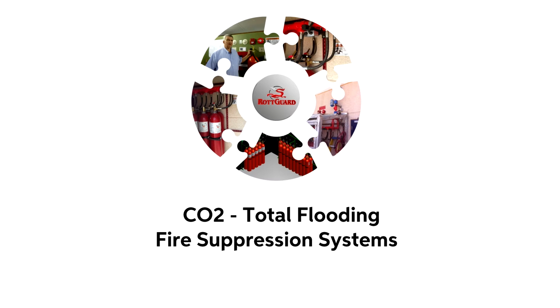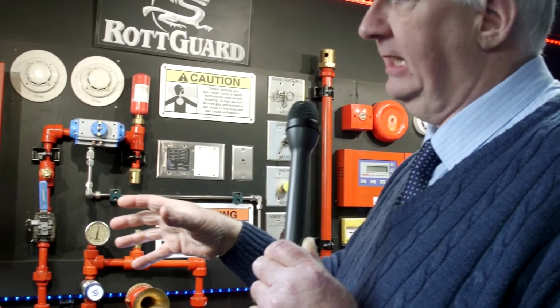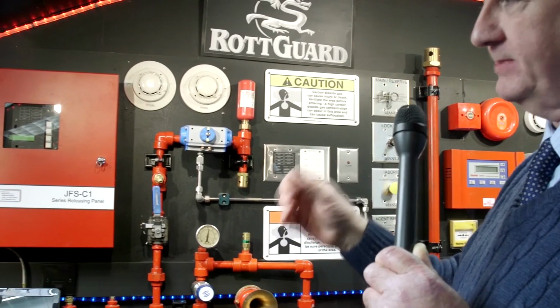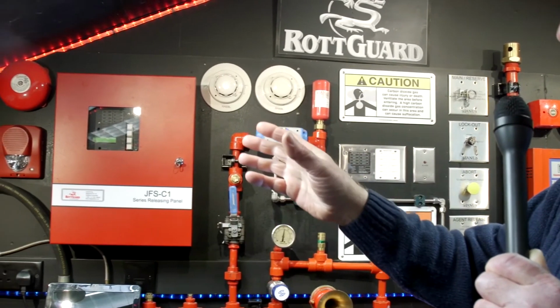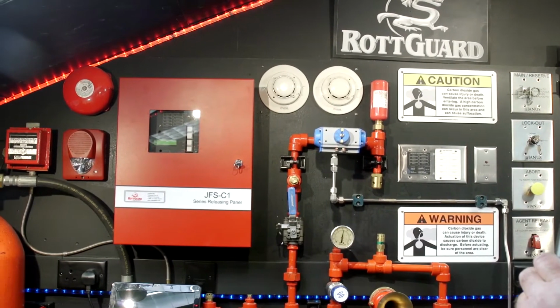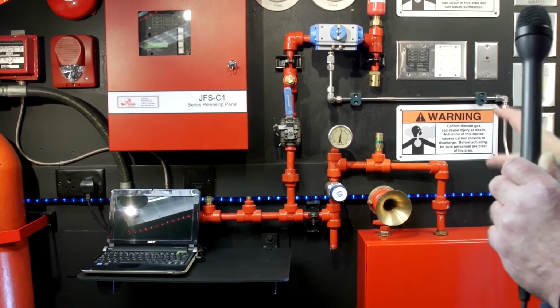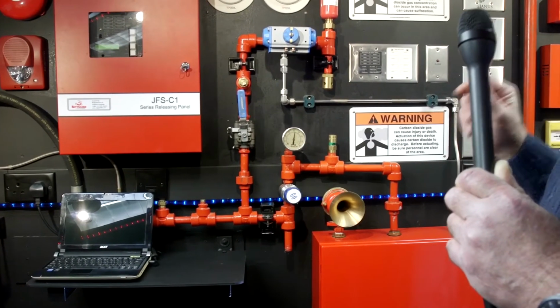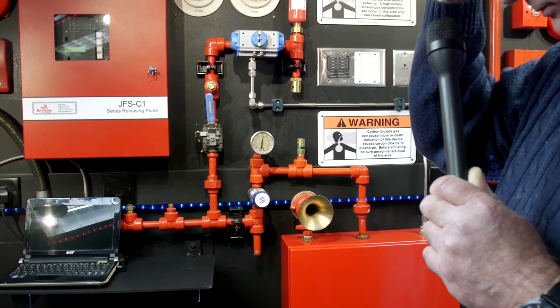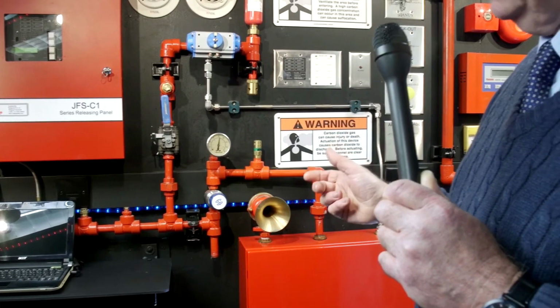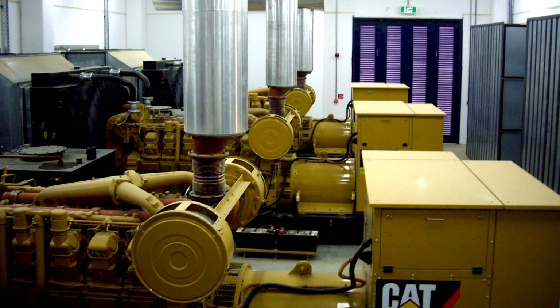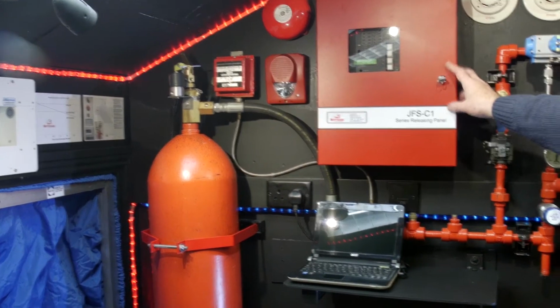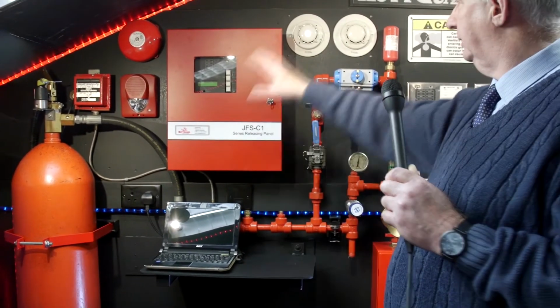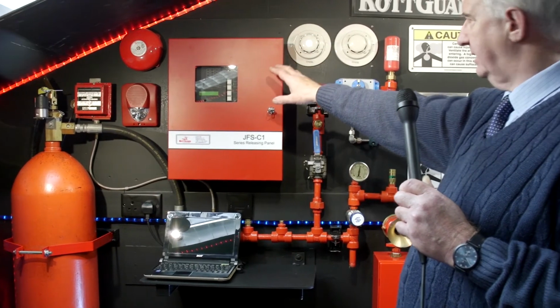CO2 is used in areas that can't be totally enclosed, and they're commonly used in ships' engine rooms because CO2 is less expensive than any of the clean agents associated with these. This is a mock-up of a system used to protect 4 cat generators in one of Al Marai's factories in Saudi Arabia. It's represented down here, small scale photographs. This is one of 27 cylinders that were employed in that system. This is the electronic control panel used to control the detectors. This system is UL listed.